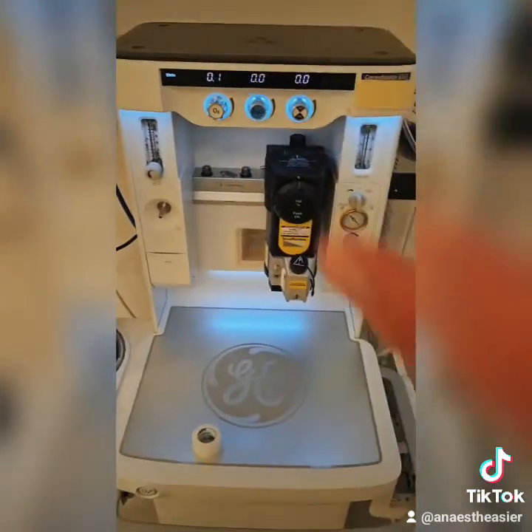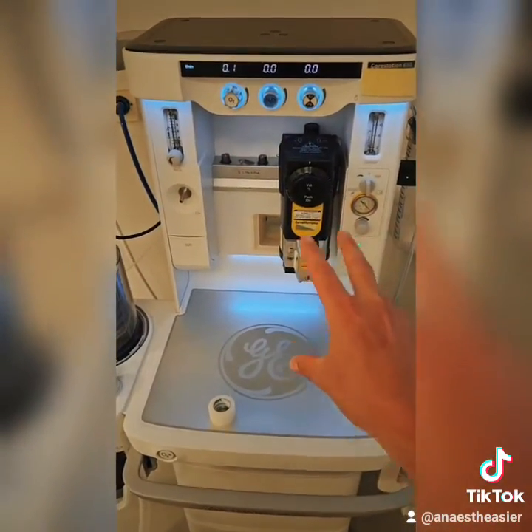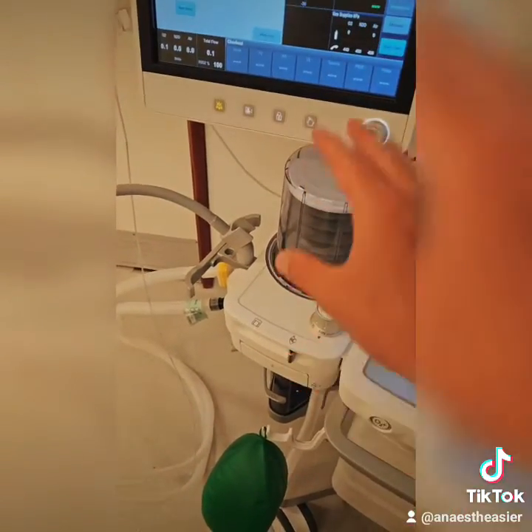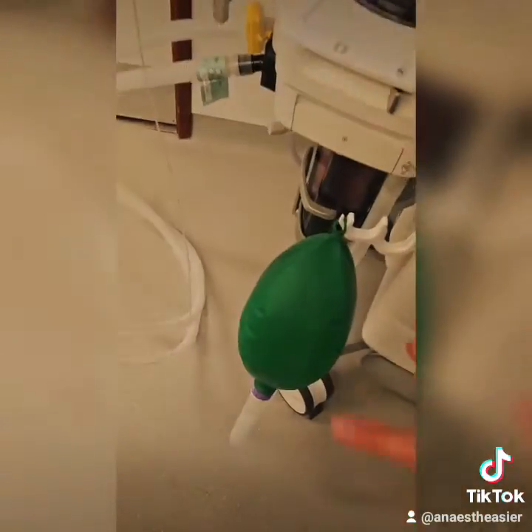So that's it, literally the whole anaesthetic machine. All it does, this bit gives a known concentration of gases and vapours, and then the ventilator lets you push air in and out of the patient. That's the whole machine. You then have some extra bits with some suction. You've got the soda lime to absorb CO2 and the breathing bag to help support the patient's breathing, but that's it.